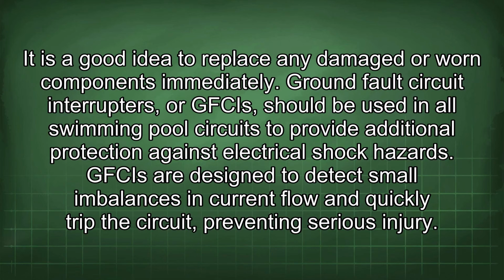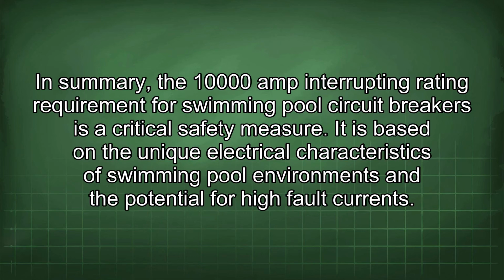Ground fault circuit interrupters, or GFCIs, should be used in all swimming pool circuits to provide additional protection against electrical shock hazards. GFCIs are designed to detect small imbalances in current flow and quickly trip the circuit, preventing serious injury. In summary, the 10,000 amp interrupting rating requirement for swimming pool circuit breakers is a critical safety measure. It is based on the unique electrical characteristics of swimming pool environments and the potential for high fault currents.